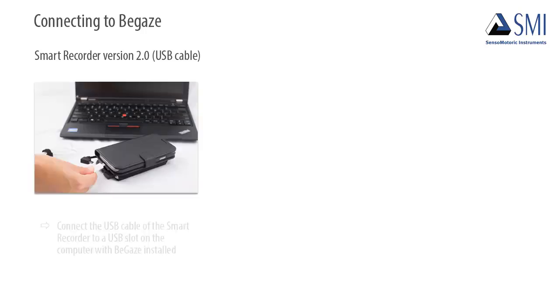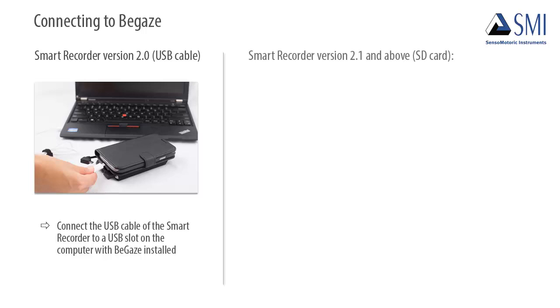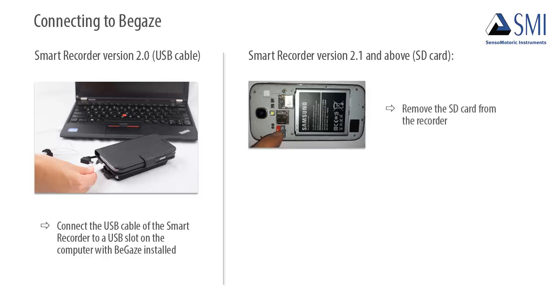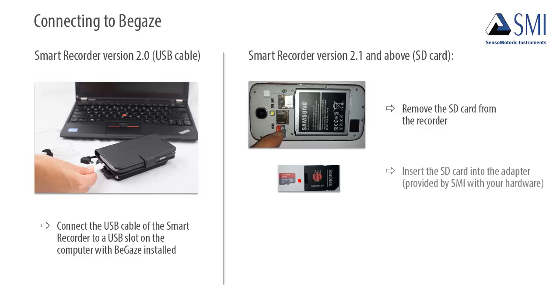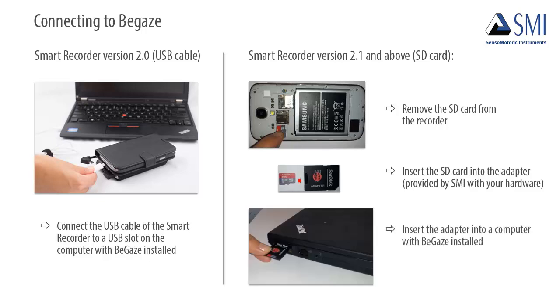For Smart Recorder version 2.0, connect the USB cable of the Smart Recorder to a USB slot on the computer that has BeGaze installed in order to connect to BeGaze. For Smart Recorder version 2.1 and higher, perform the following steps. Remove the SD card from the recorder. Insert the SD card into the adapter that was provided by SMI with your hardware. Then insert the adapter into a computer with BeGaze installed.